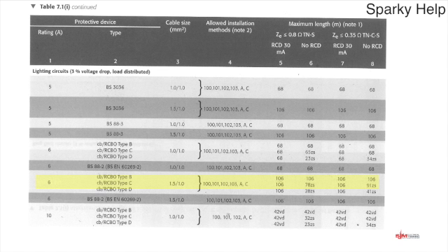You'll notice some down on the bottom, on the 10 amp at the very bottom of the page down here, they say VD, and that means they would fail on volt drop. So you'd have to make sure you stayed less than 42 meters if you were looking at this one here and installing 1 mil on a 10 amp. Okay, so you would have to keep the lengths of run quite small. I say quite small, 42 meters is quite a long way to go, but it's a very quick way. So if anyone ever asked, did you work out using the adiabatic equation? Your answer is no, of course I didn't, because I looked in the on-site guide and this gave me my lengths of run, and I've installed it as per these tables.